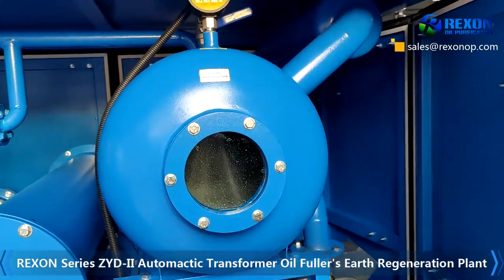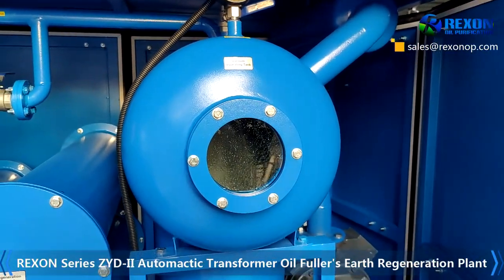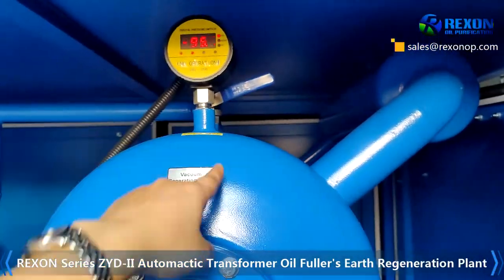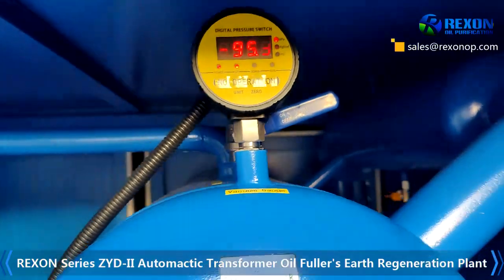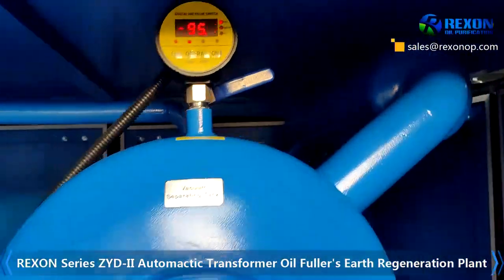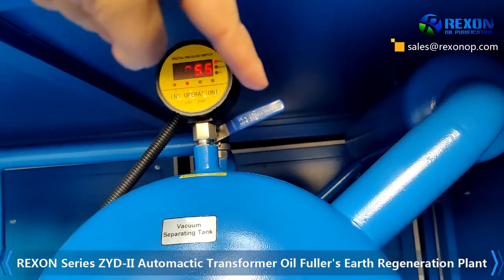If the oil is still having a lot of foaming and oil bubbles, keep the vacuum valve just above like this and open it just a little bit. After the oil foaming has disappeared completely, you can close this valve. Remember to close it.